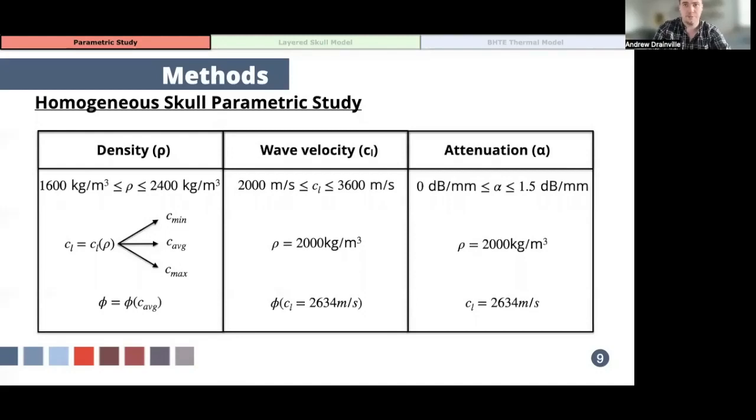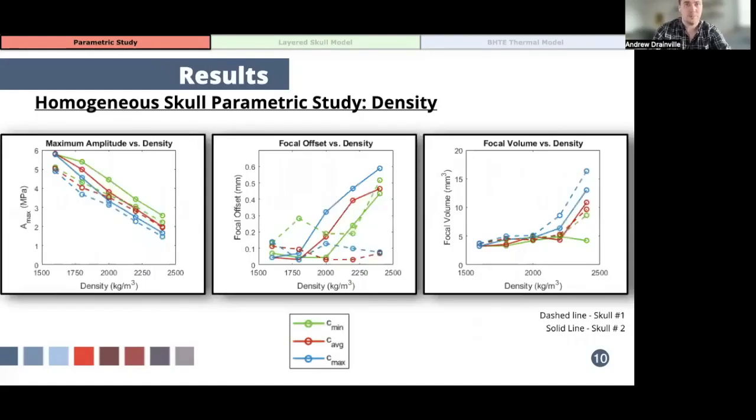So first looking at the results from varying density, here we can see the results with the minimum, average, and maximum wave speed plotted as a function of density, where you have dashed line for skull sample one and a solid line for a second skull sample. On the left, we can see a decrease in the acoustic amplitude at the focus with increase in density, which is expected as higher densities and the associated increase in speed of sound will increase the amount of energy reflected from the skull. The shift in the focal position showed little sensitivity to changes in skull density and speed of sound. While there's a greater focal offset for higher density values, the maximum offset reached a value of only about 0.6 millimeters. And then finally, on the right, we can see how the focal volume changes with density and speed of sound. The significant increase in focal volume is seen due to the effects of defocusing, which occurs most at higher density values where there is the most disagreement between conversion algorithms.